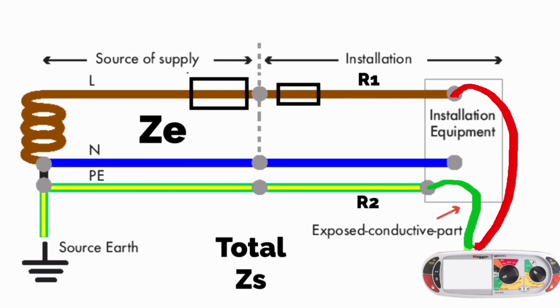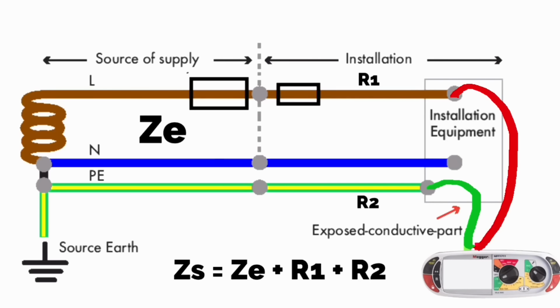The total earth fault loop impedance of a circuit measured in ohms is found by ZS, being the total earth fault loop impedance, equals ZE, the supply authority's cable's impedance, added to R1, the line conductor's impedance, added to R2, the circuit protective conductor's impedance. The formula is ZS equals ZE plus R1 plus R2.